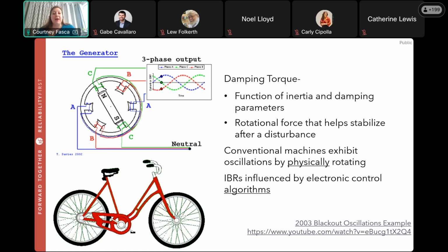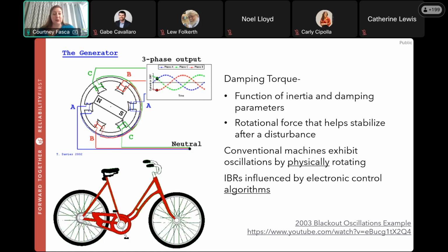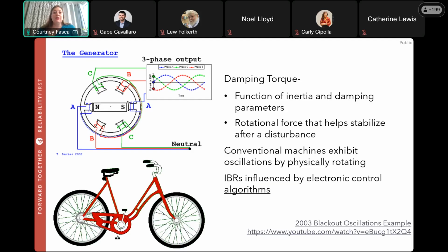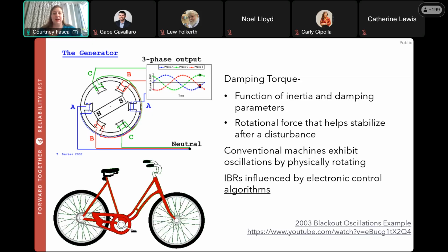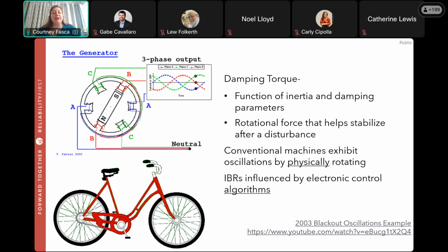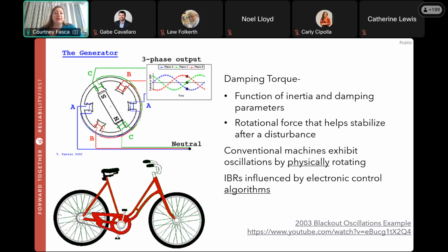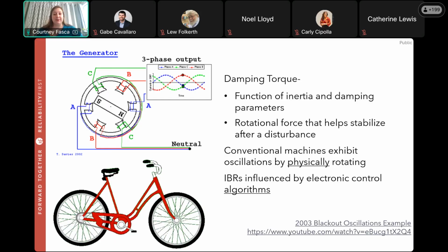On the power grid, we have devices called FACTS, the Flexible AC Transmission System devices, and those enhance the controllability and power transfer capability of AC transmission systems by rapidly managing real and reactive power flow. So for example, that would be an SVC, a static VAR compensator, which can help restore stability. When it comes to oscillations, conventional machines, like the one shown in the top left corner, exhibit oscillations by physically rotating. Meanwhile, IBRs create oscillations or waves by electronic algorithms. No momentum, no inertia, just algorithms.